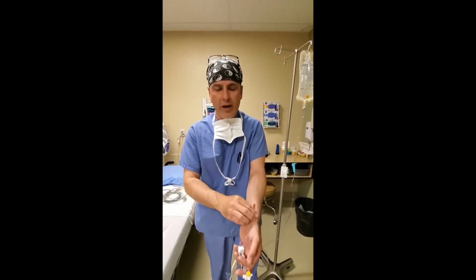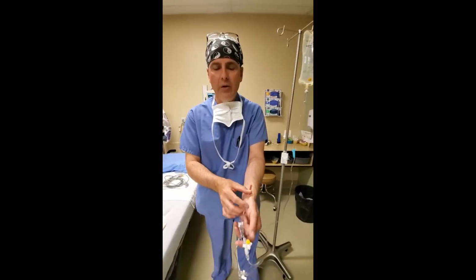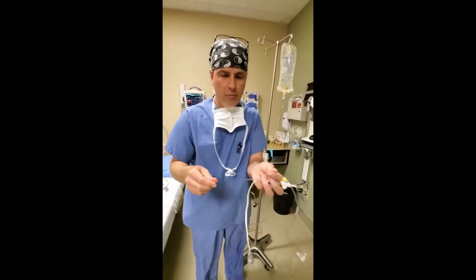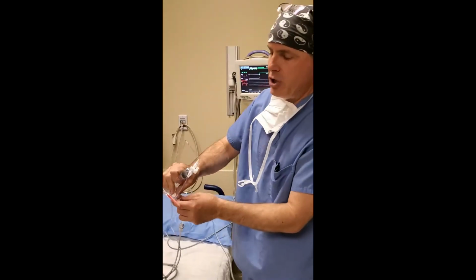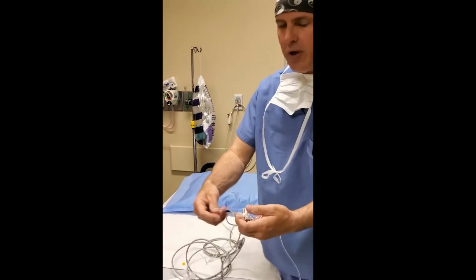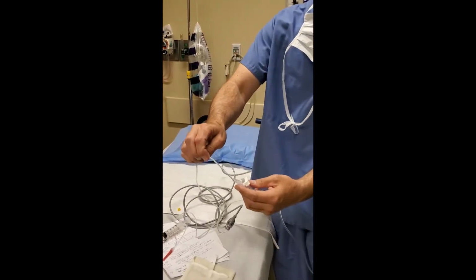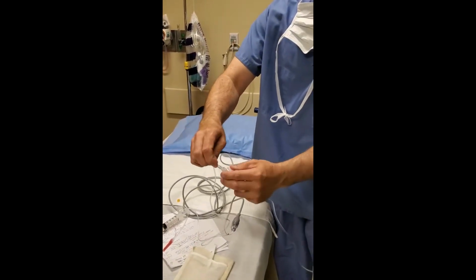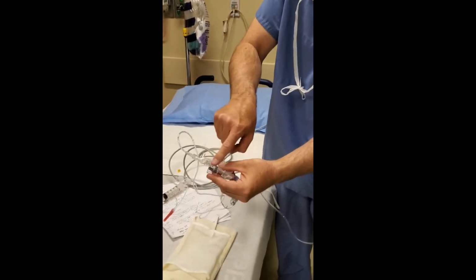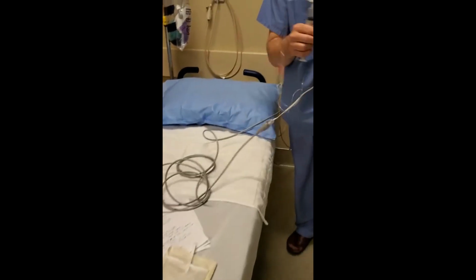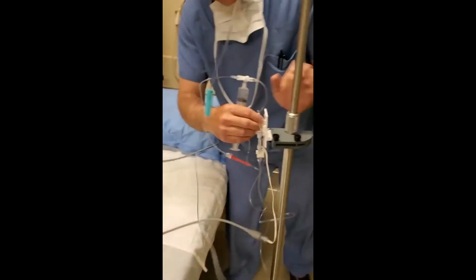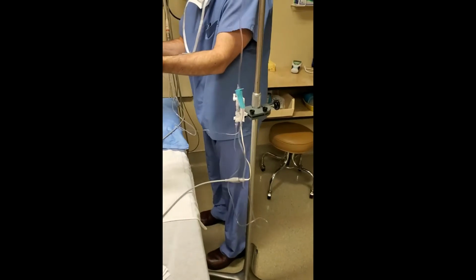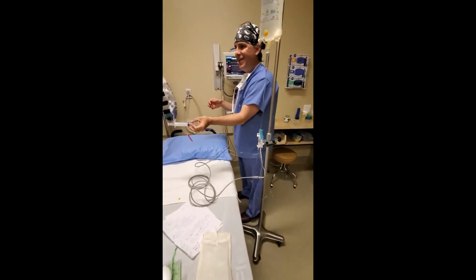So we put this arterial catheter in right here—this is a needle, obviously. We're going to shut it off to the patient; you always know which way the patient's side is because that's the hard tubing, you can squeeze it and tell. Turn it off to the patient, and that opens the transducer to air. We're going to pretend we have this set in here. Now pretend this is in my artery.